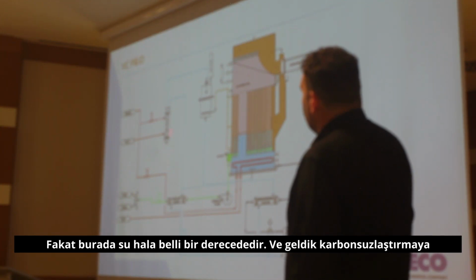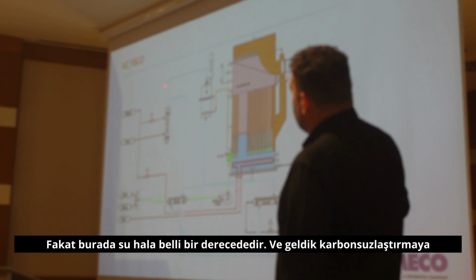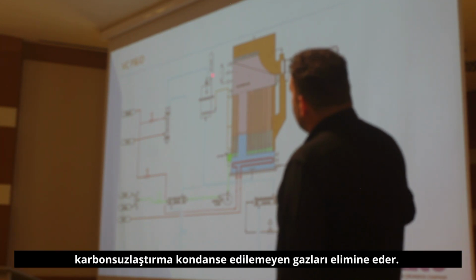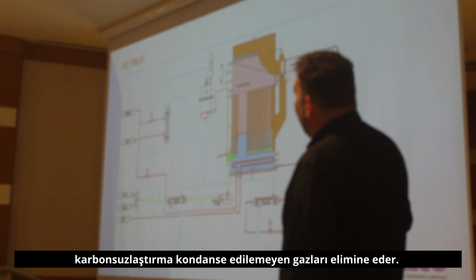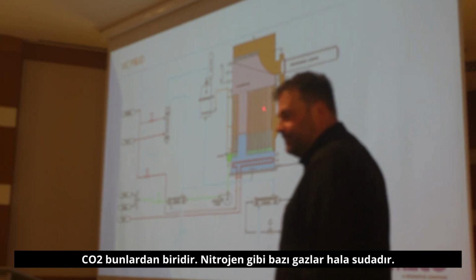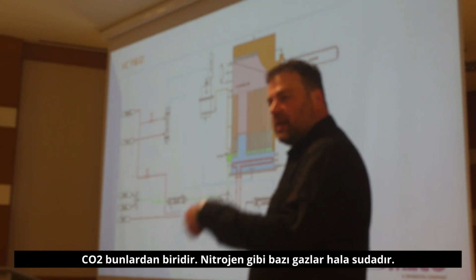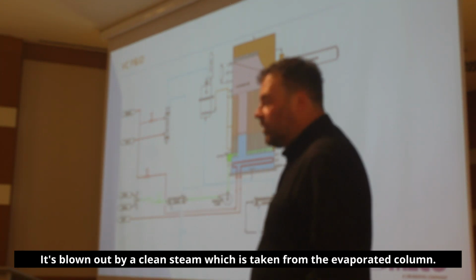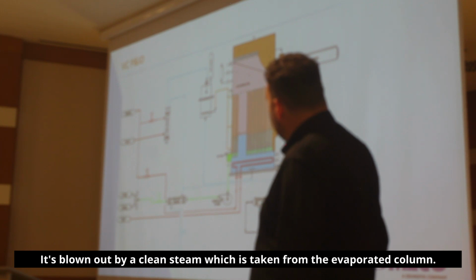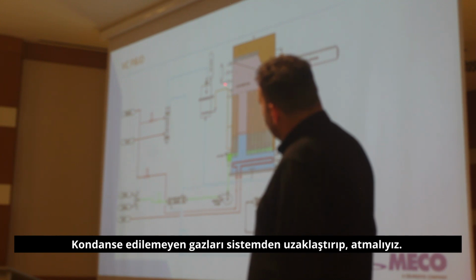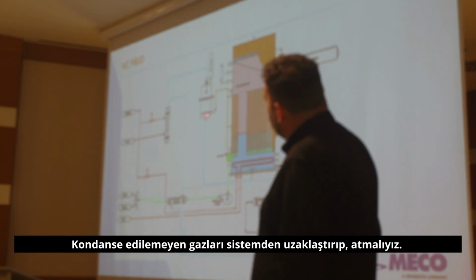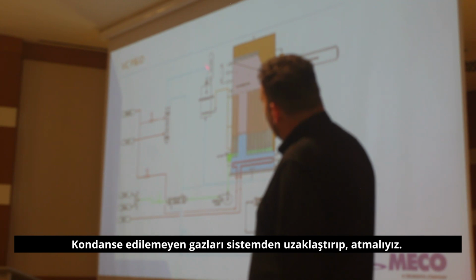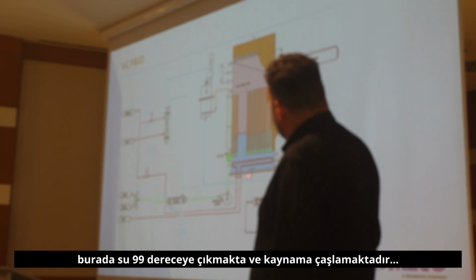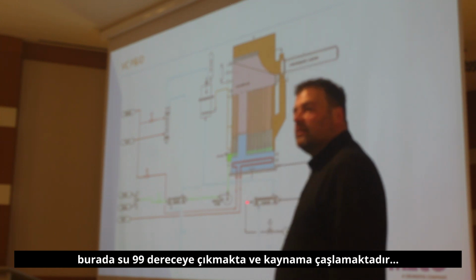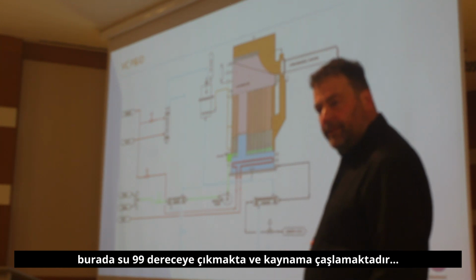But here, the water is already at a certain temperature, and then we come into the decarbonator. The decarbonator removes our non-condensable gases, CO2 is one of them, there's also nitrogen and other gases still in the water, which are blown out by clean steam taken from the evaporator column, we'll come to that later, blowing out the non-condensable gases up through the vent. So right here, the water is already 99 degrees Celsius, nearly boiling.